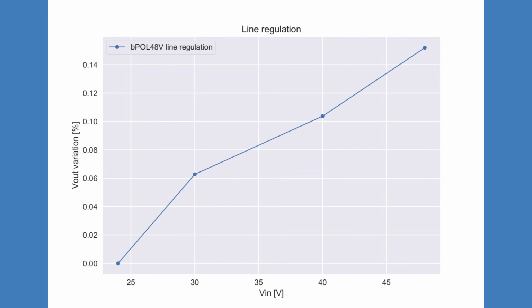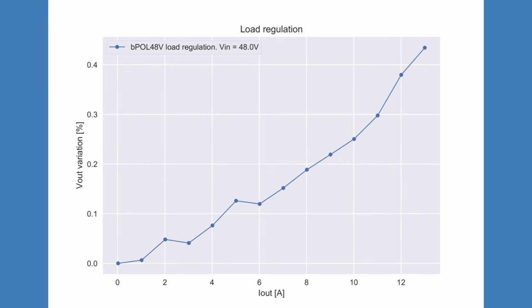Next is line regulation. Sweeping the input voltage from 24 to 48 volts, the output variation stays within about 0.15%. This shows the control loop remains very stable even with the large bus variations typical of 48-volt architectures. Load regulation: from no load up to full load, the output changes less than about 0.45%, demonstrating tight voltage control even during current demand changes.